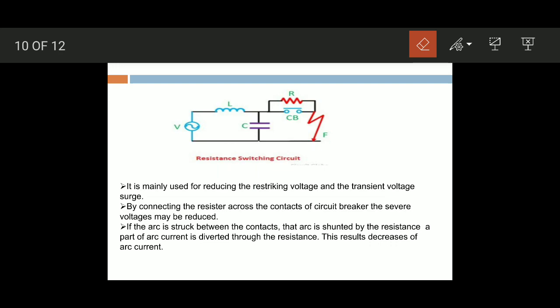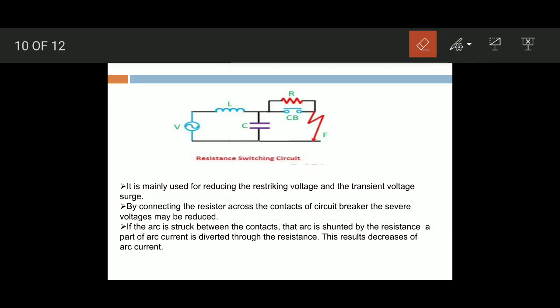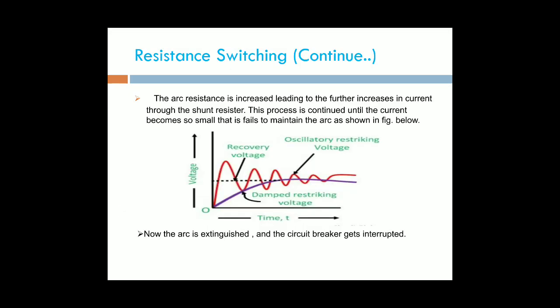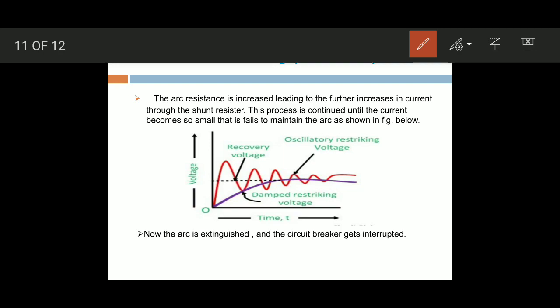Thus the arc resistance is increased, leading to further increases in the current through the shunt resistance R. This build-up process continues until the current becomes so small that it fails to maintain the arc, as shown in the figure.